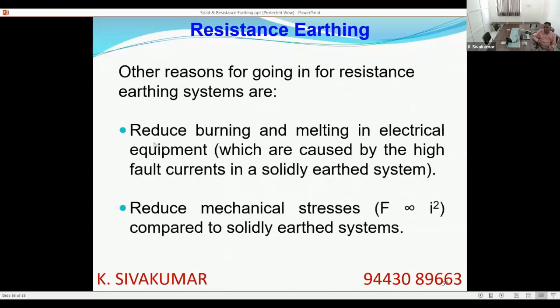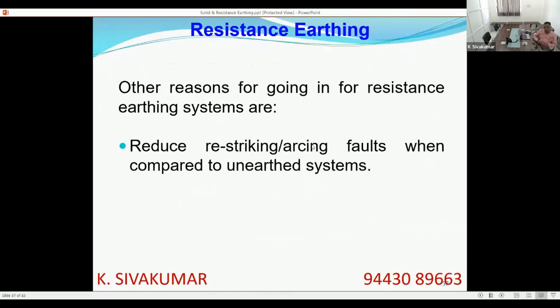Other reasons why you go for resistance earthing: reduce the burning and melting in electrical equipment. Solid grounding, we said, very high current. In resistance grounding, you are limiting the earth fault current. So that much burning and melting is minimized. Similarly, mechanical stresses are reduced. The forces developed during short circuit, electromechanical forces or electrodynamic forces developed during short circuit, the formula is force is directly proportional to square of the peak current. So if you provide a resistance, the RMS current reduces, fault current reduces, the peak fault current reduces, the force reduces, the stresses reduce. Then arcing faults can be minimized because you are limiting the current. Restriking fault or arcing fault can be minimized.